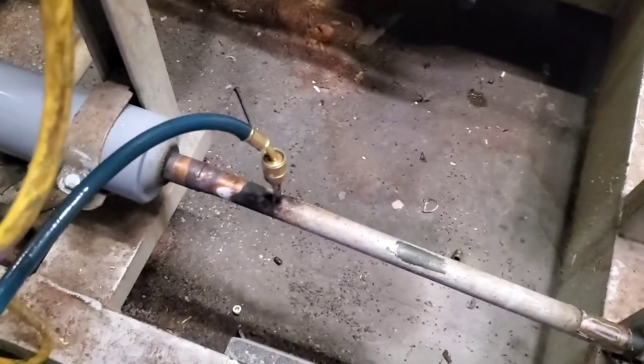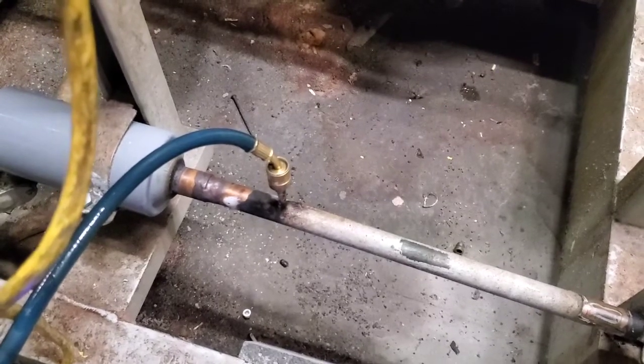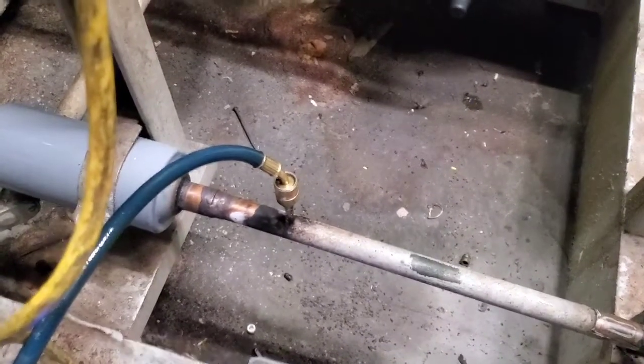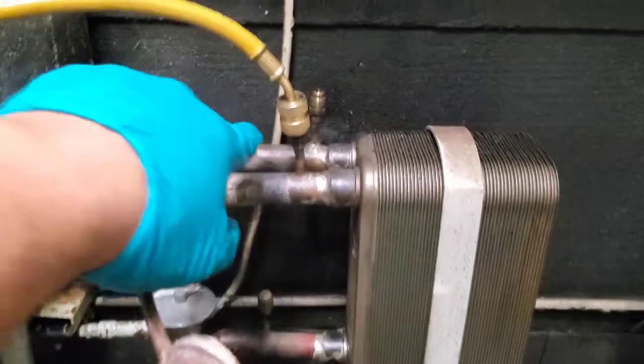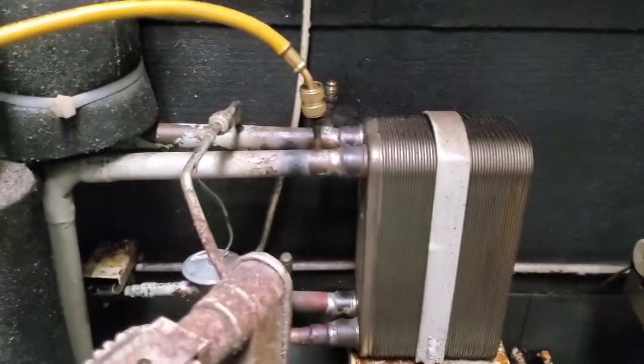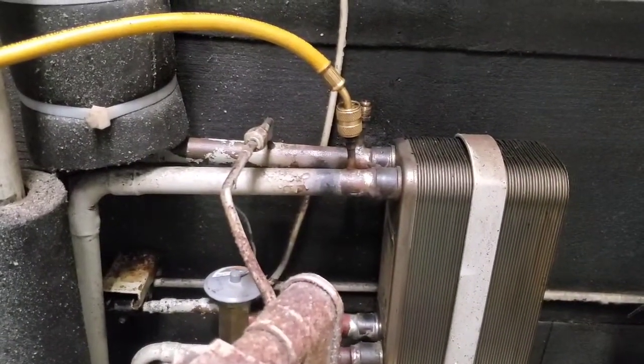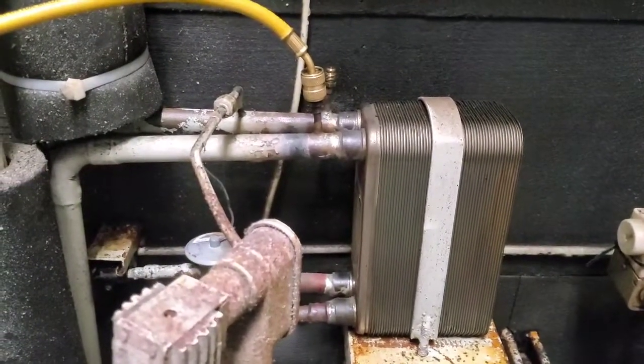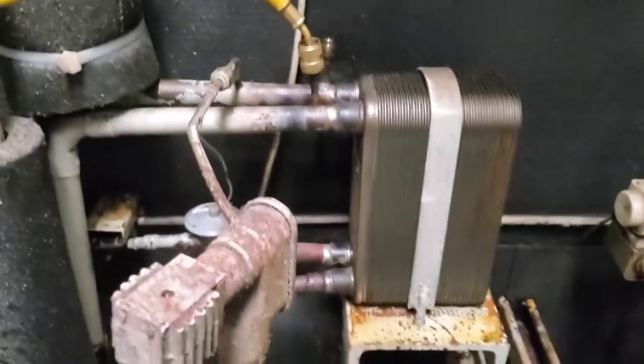We're pulling gas off of this yellow hose, goes into our gauges, out of the blue hose, comes into our recovery machine, out of the recovery machine, and back into the liquid line. Again, we're recovering it out of a section of the chiller and putting it in a different section of the chiller that's isolated from each other. And since it's impossible to get all the oil out of this system that we've got isolated, we're pulling off of the top of that section of the circuit that we're working on. That way we have a minimal chance of pulling in any oil into our recovery machine. If we were pulling off the bottom, there would be a very big chance of us pulling oil into our recovery machine doing damage. But here off the top, it's never given us any trouble in the past.